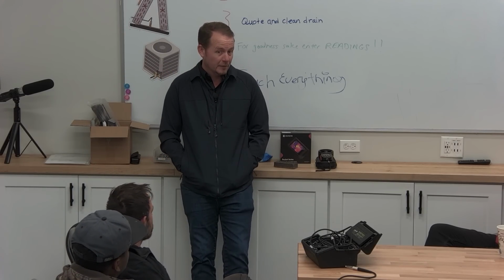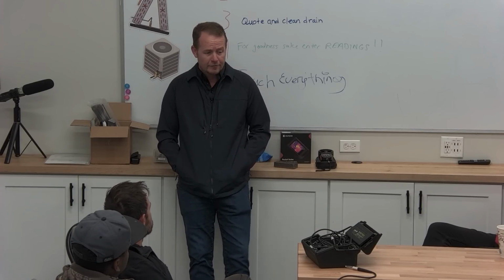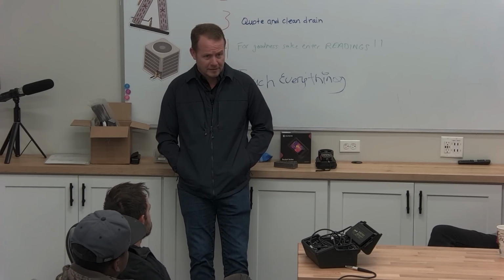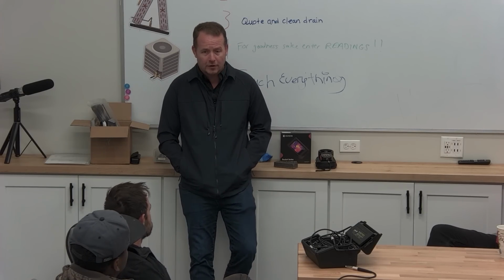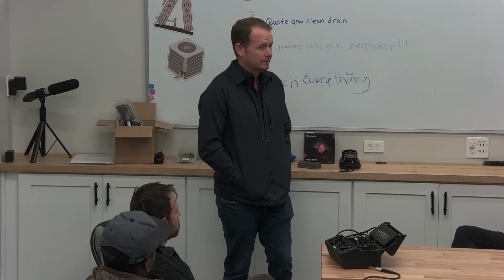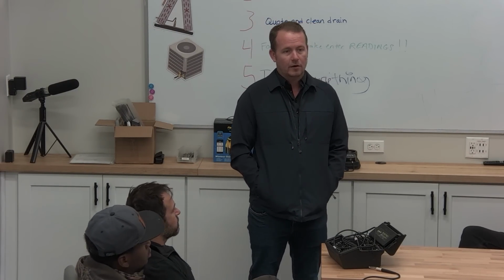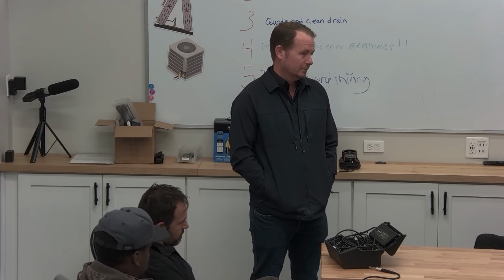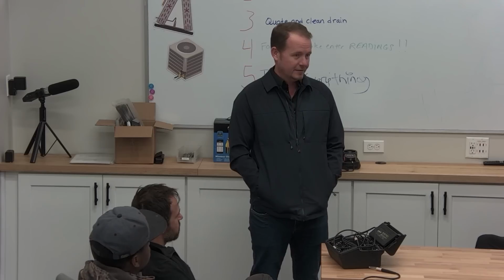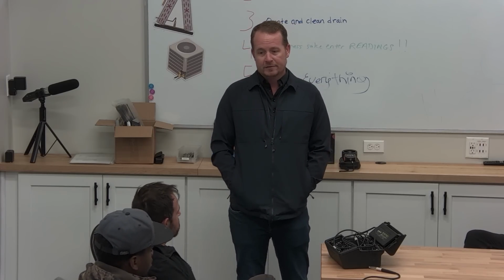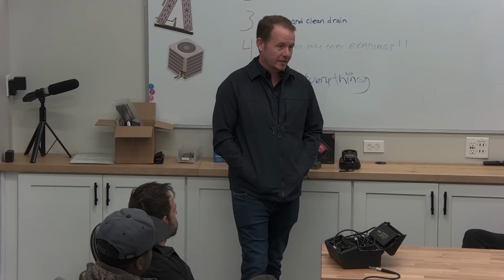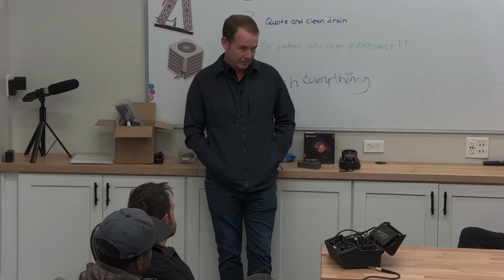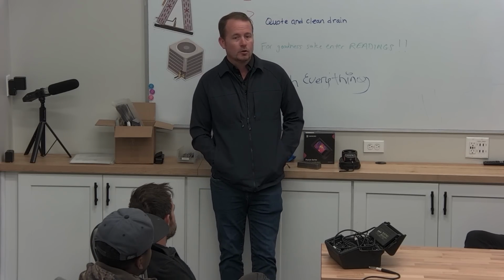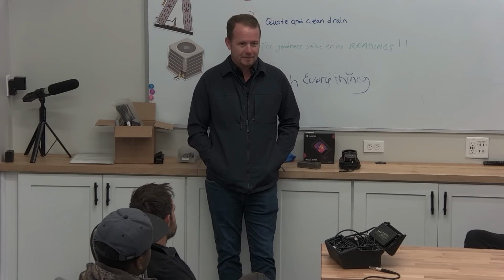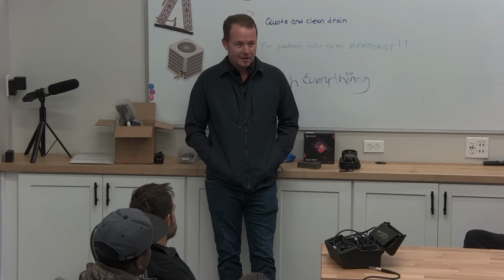On the flip side, for any of you putting coils in or replacing something that was supposedly leaking, what's the very first thing you do when you show up? Re-diagnose. You reconfirm that 100% of the time. And when you're reconfirming, you're turning your spidey senses on again too. You're not just reconfirming, the goal should never be to try to prove somebody else wrong, but have a little fun with it.